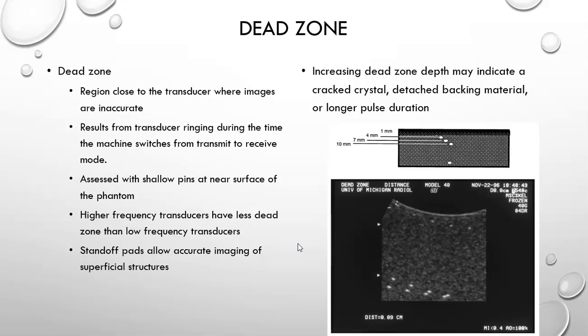If you do need to image in an area near the face of the transducer, what you do is you use a standoff pad in order to move the transducer back a little bit and provide yourself some distance to those first reflectors. This also allows the focus to come into play, because on many machines, the closest to the transducer you can get the focus may be 1 centimeter or so. And if you're looking at a structure at 1/4 centimeter, then that's simply too deep of a focus.